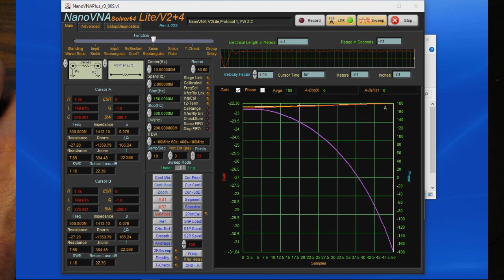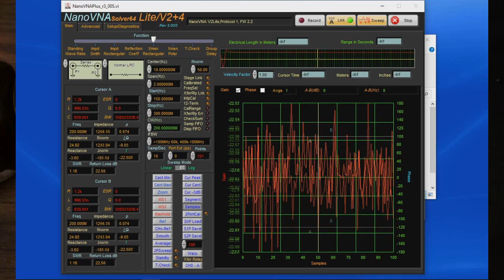Let's go ahead and adjust this down a little bit. We'll go to 50. Let's just reset our averages. Watch that counter. Right there you are. And that was 100 samples right there. Let's try going even faster. Let's try 25. Right there you can see it can't keep up. Now again, we could change that E1 register. That'd certainly throttle it. Let's just bump it up a little bit. Boy, we're right on the edge right there. So let's go back to 101 data points, and we'll select again CW mode at 200 megahertz. And again, we can see this is collecting data at roughly 20 milliseconds. And 20 milliseconds at 101 data points is roughly 5 kilohertz.